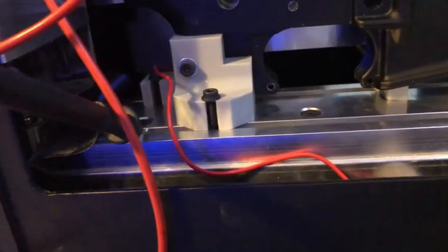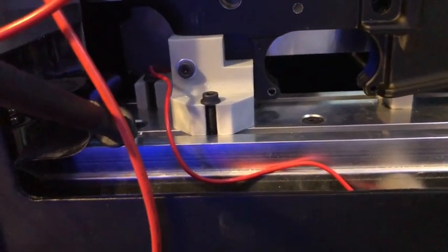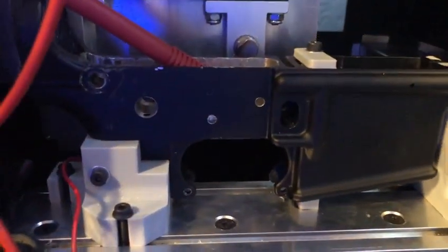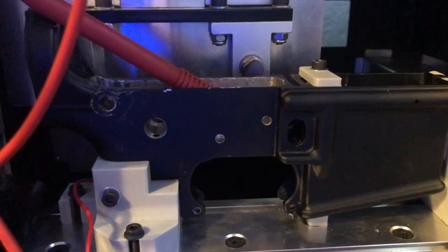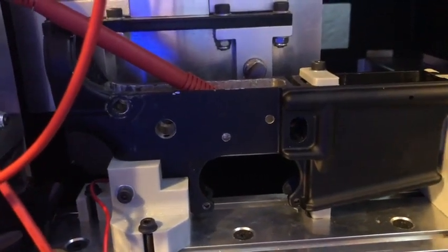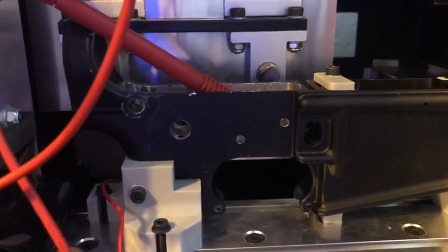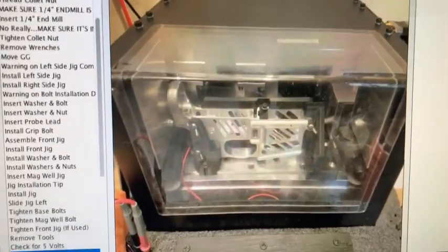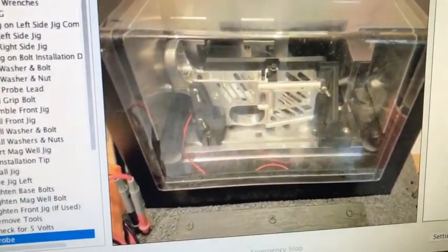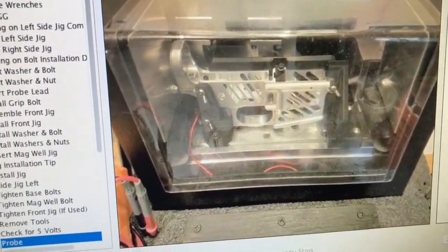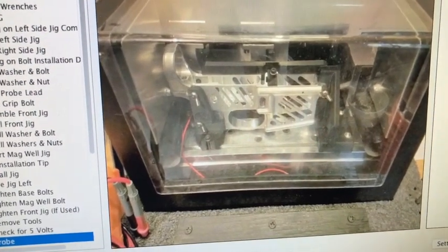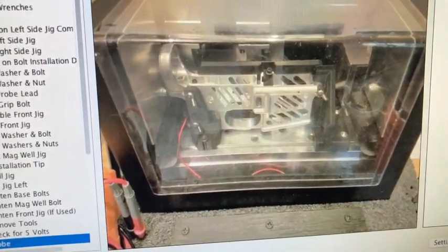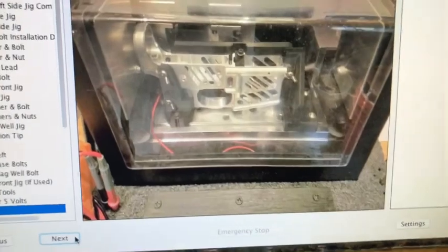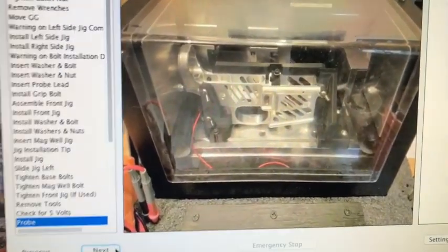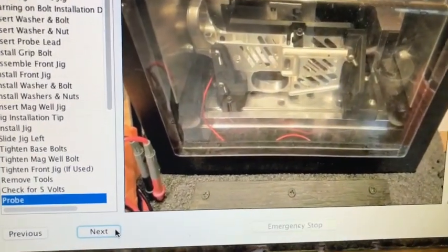Typically, I place the negative end of the fluke on the T-table, and I put the positive lead inside the pocket where it is directly touching the aluminum of the lower. You are receiving your 5 volts on the lower itself. I recommend checking on the lower and not the probe wire, because when it probes, it's looking for the 5 volts on the lower. So if you have 5 volts there, you're safe to begin the probe.